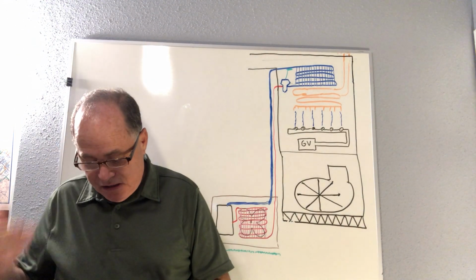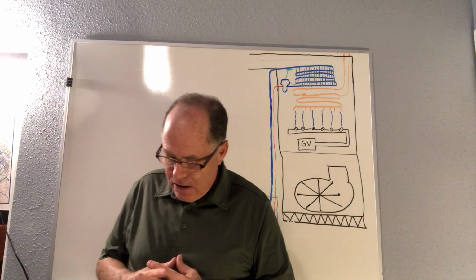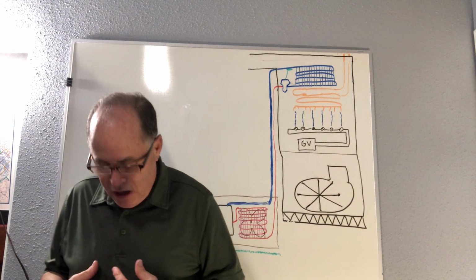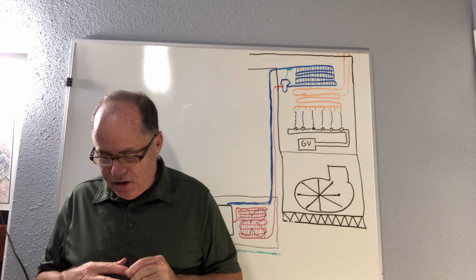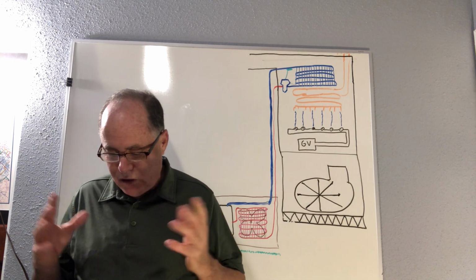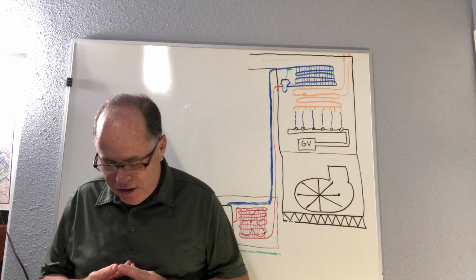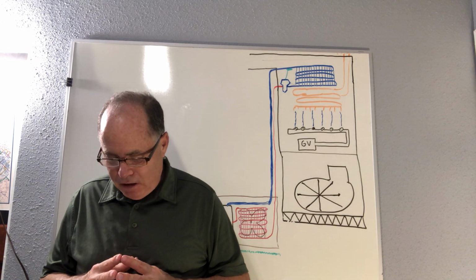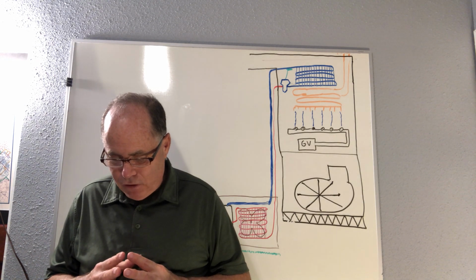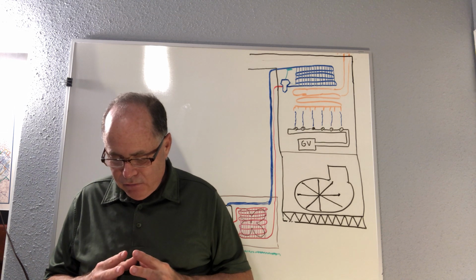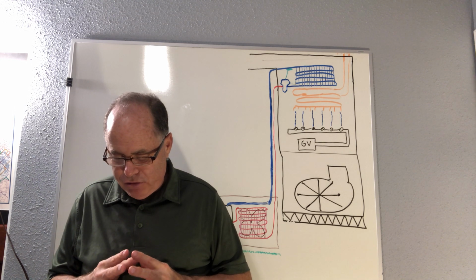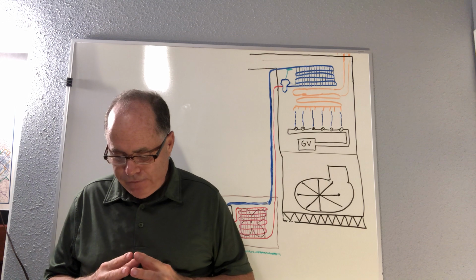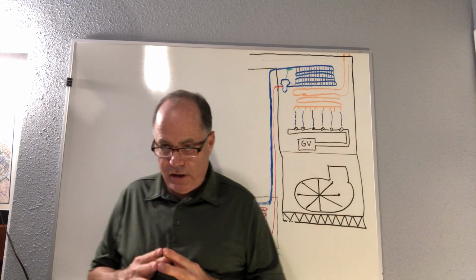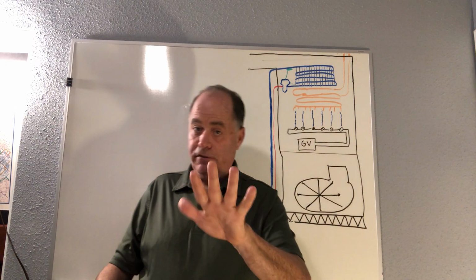Now, here it talks about refrigeration coils, which really means generally evaporator coils, could mean chilled water coils. Refrigeration coils shall not be installed in conjunction with forced air furnace where circulation of cool air is provided by the furnace blower unless the blower has the capacity to overcome the external static pressure resistance imposed by the duct system in the refrigeration coil at the airflow rate for heating or cooling, whichever is greater. It's always going to be greater for cooling. Okay, we have this general principle.